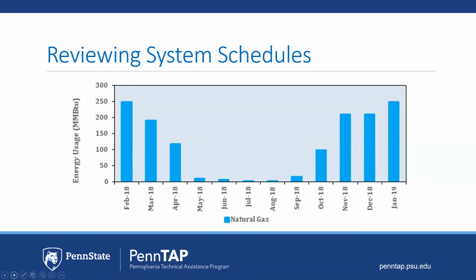A common opportunity that has immediate improvement includes reviewing the heating system schedules. In this chart, it was a natural gas boiler that was reviewed. We note that there is a hot water tank attached to the natural gas, and that is why we see some natural gas in the summer months. But it was asked of the client if we needed to turn on the boiler when they did.